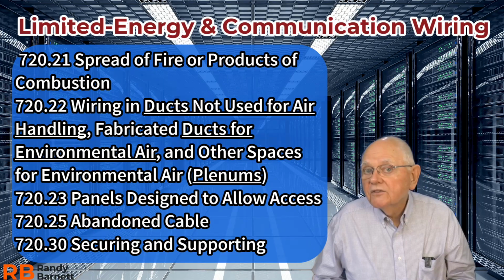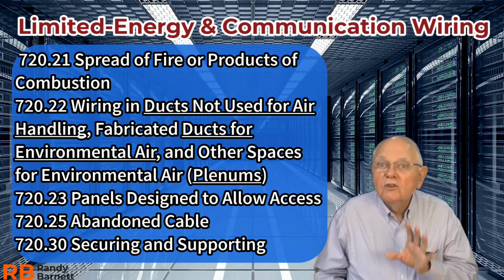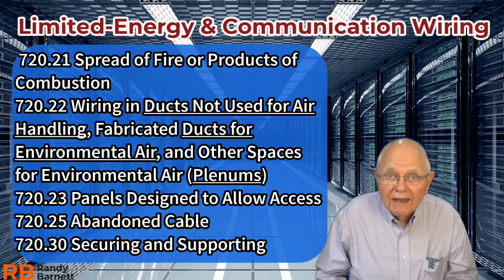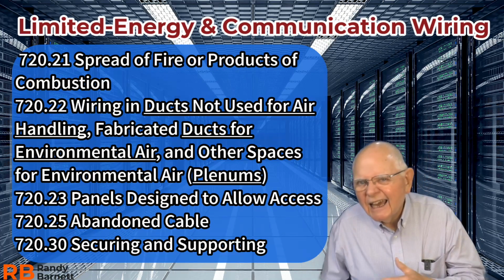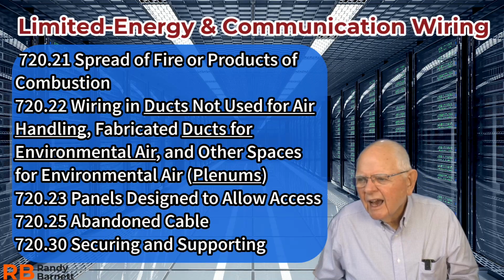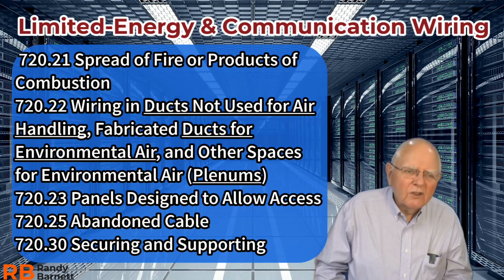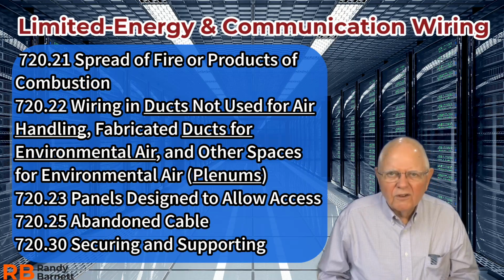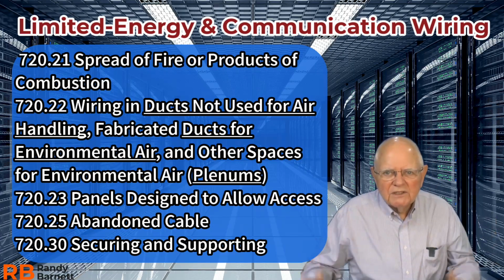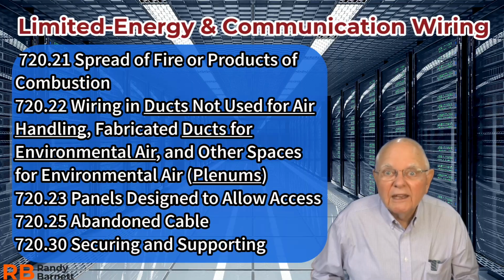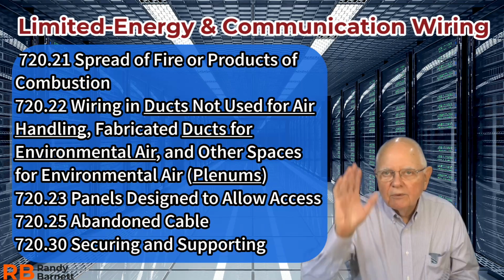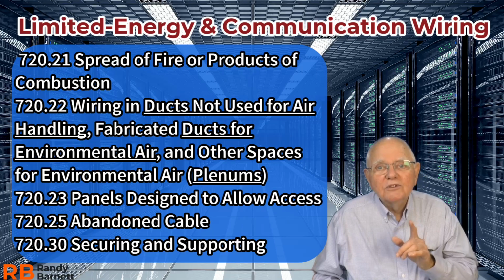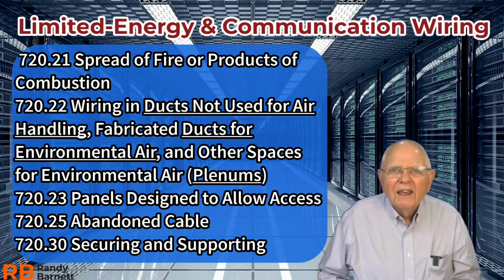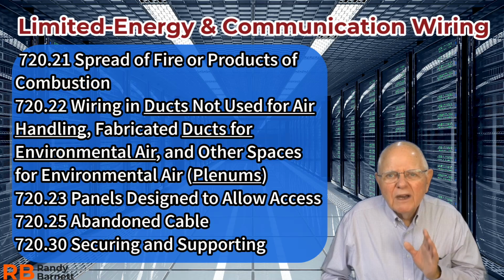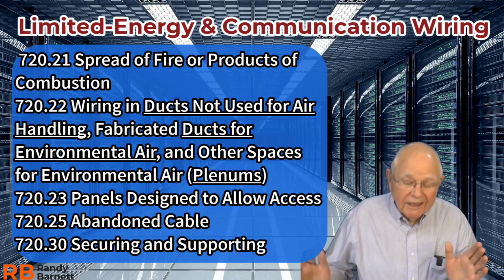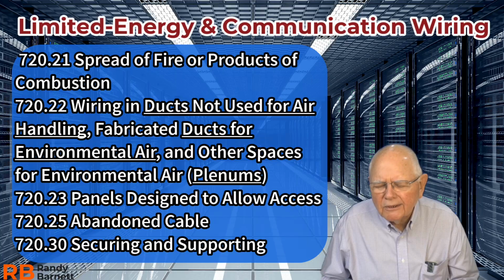I can use independent support wires as one way, but if I'm going to use those independent support wires, they have to be distinguished by colors or tags, it talks about. So what do I do? I probably get all of those independent support wires together before I ever first climb the ladder. Maybe lay them out on a piece of cardboard and spray paint them some color or whatever, okay? And then I put those up in the ceiling. Cable ties, it says, if I use cable ties in these areas, the cable tie must have low smoke properties.